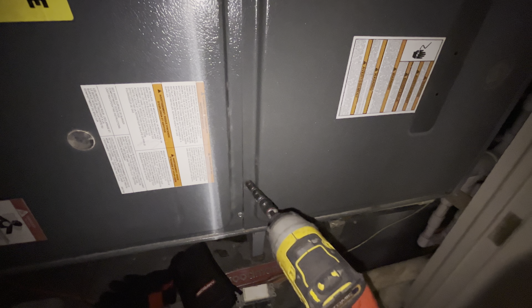So count the fault codes. That's 6 flashes. Check again. So 6 flashes. From experience, I know that 6 flashes, that's the flame rollout. So I'm gonna go right there and I'm gonna show you where your flame rollout switch is. I'm gonna go ahead and reset that.